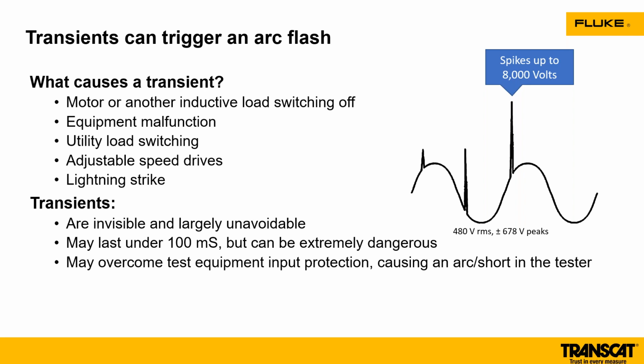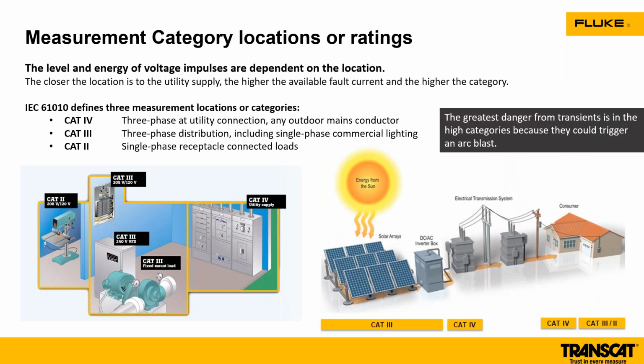If you're connected to some type of equipment making that measurement, that transient now has the ability to go through your meter. So that's why category ratings on your meters are important, knowing the category rating and knowing the environment that you're working in. This is a great slide because I like to give an education piece about your category environment. This is different than the PPE category ratings. That's part of your PPE category. This is part of your electrical environment.